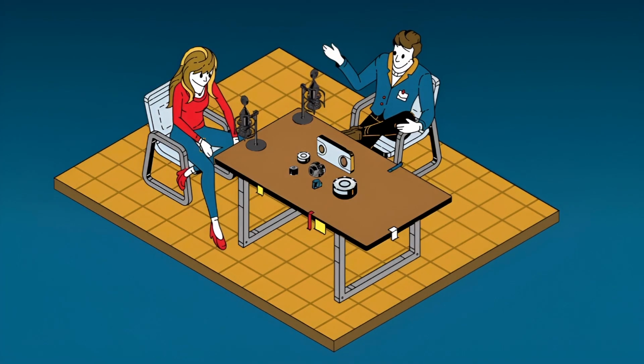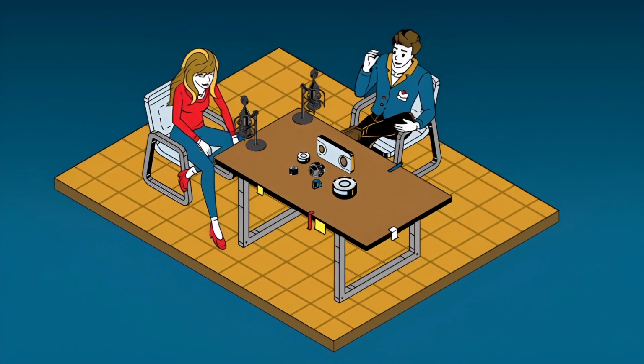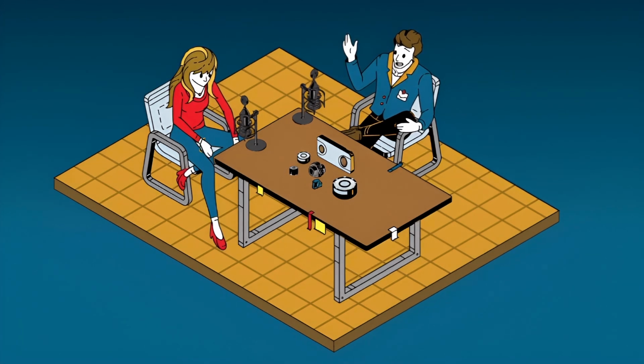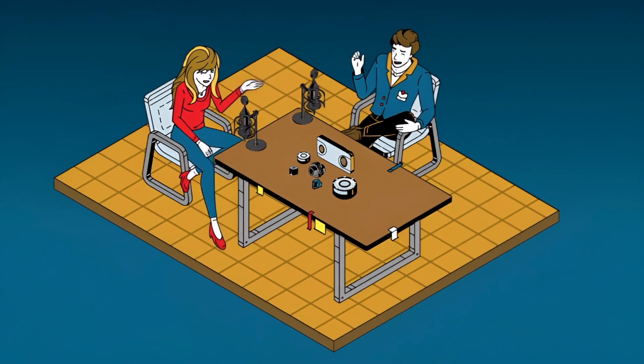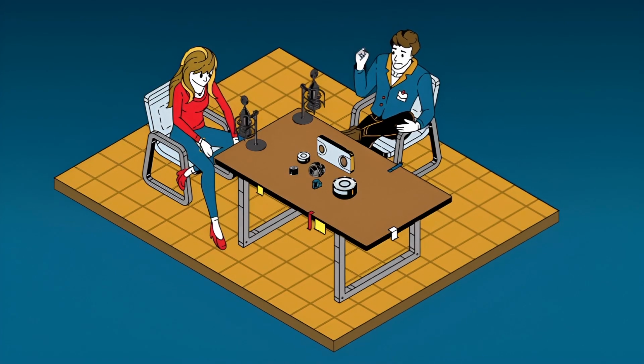Load cells are engineering marvels. They've got exceptional design, precise machining, materials chosen specifically for stability. They are engineered to be reliable. So they should be immune to failure then. Highly resistant, but never immune. At the end of the day, they're still electronic devices. And they're susceptible to two main things: being pushed past their physical limits, and of course, environmental conditions that mess with their internal stability. Okay. So our goal is to dive into those vulnerabilities and, maybe most critically, identify the single most important thing you could do to maintain both function and accuracy.